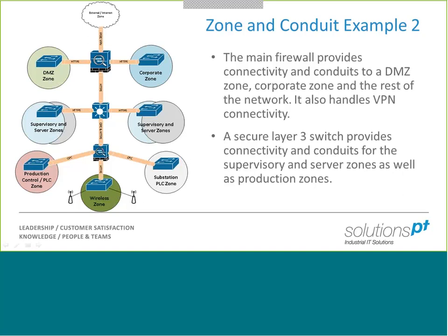It certainly would do. And obviously, just looking at this high-level diagram, we can see the wireless zone is sat at the bottom of our architecture, the bottom of our ISA levels. So we've got multiple conduits and multiple devices between our untrusted internet zone and our critical zones at the bottom. That's a much more secure approach than just having a flat network hanging off an edge internet router.